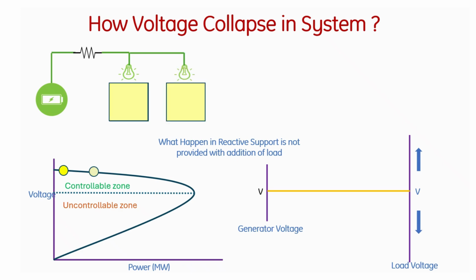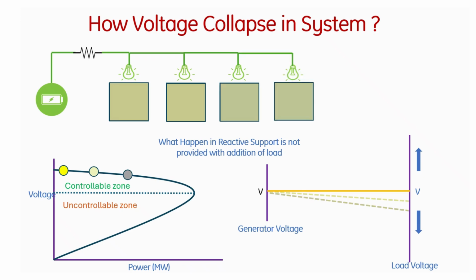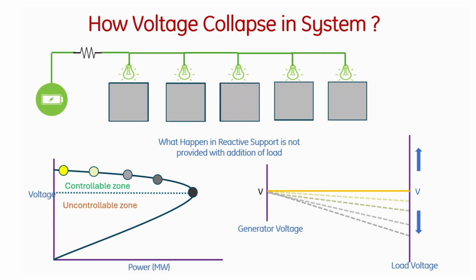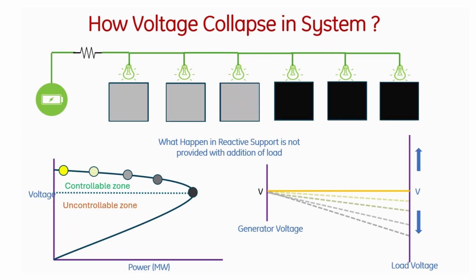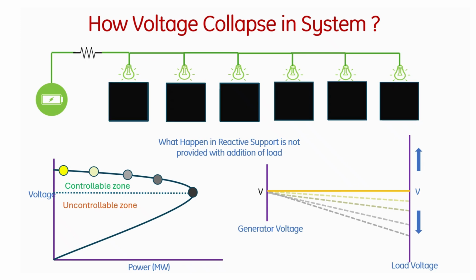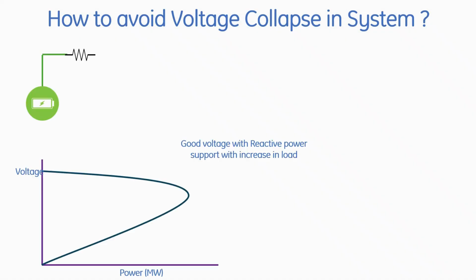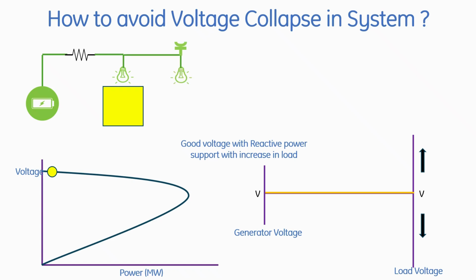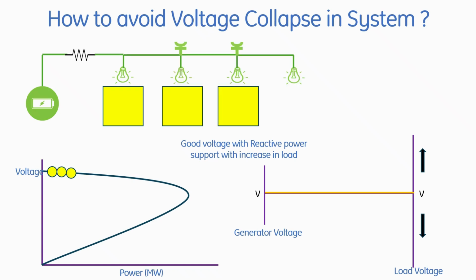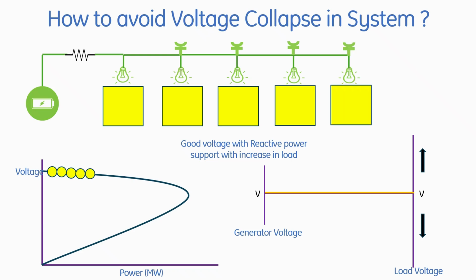As load increases and reactive power reserves get depleted or can't reach the problem area, voltage starts sagging. Past a critical point, trying to draw more power causes voltage to plummet uncontrollably. A positive feedback loop. Lower voltage, more MVAR demand, even lower voltage. Exactly. It snowballs. Voltage can drop rapidly across a whole region. That's voltage collapse. The curve shows a gradual decline, then a sharp nosedive. And the slide on avoiding collapse shows adding reactive support keeps the voltage up, pushing that collapse point further out. Right. It demonstrates the benefit of having sufficient reactive reserves and deploying them effectively.